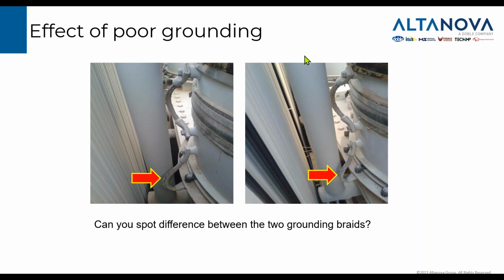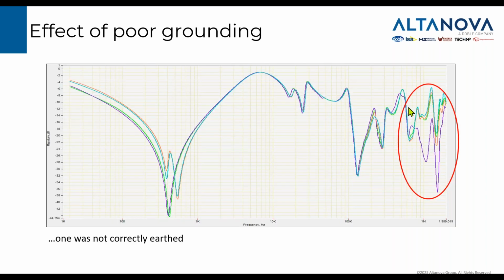Another factor, this one was the one which I tested myself. This was a transformer which was tested on site. Obviously, I pointed out two braids. These are two different phases. One braid looks like a braid, another braid looks like a braid. Their purpose is to make good connection of earthing points of different points of the housings, and they look perfectly normal. There is no visible difference between them, but apparently there was a difference.